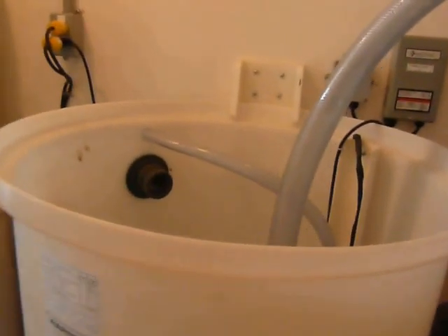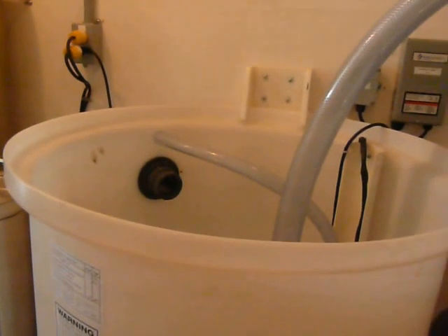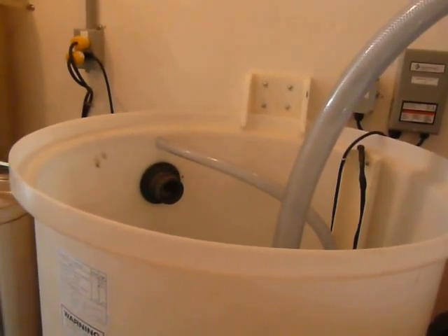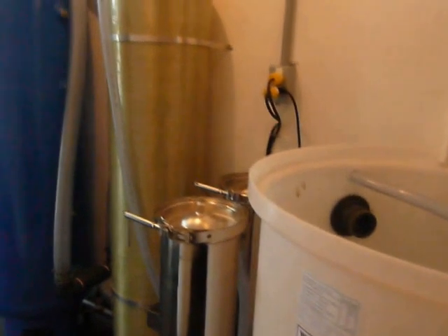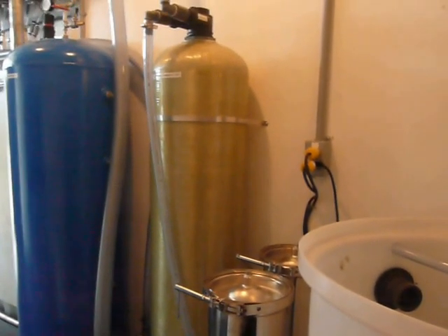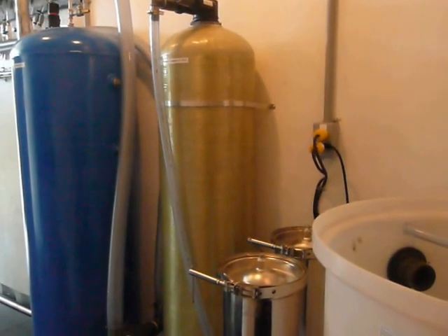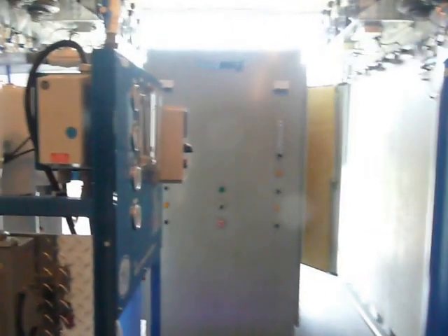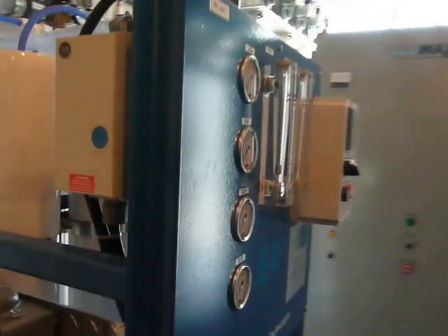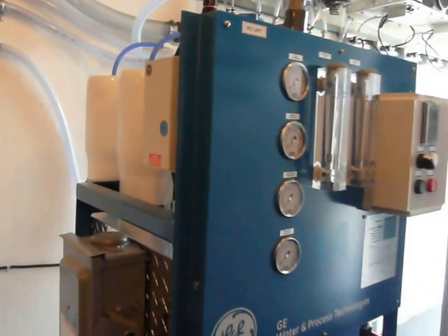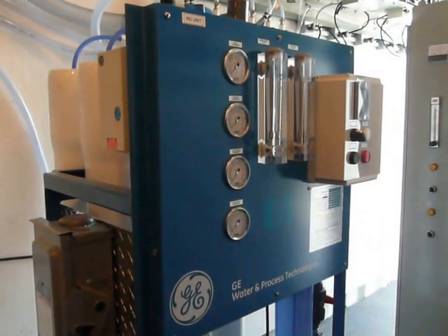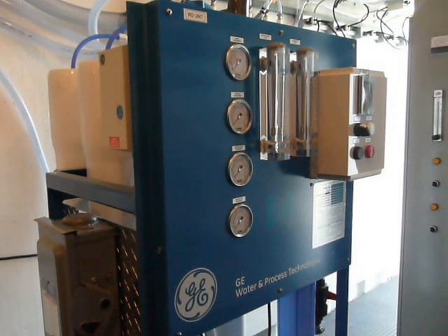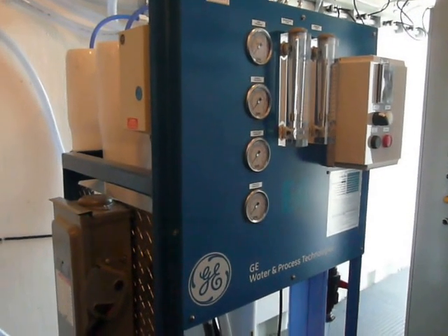Now this holding tank contains a submersible pump which directs the water into a series of filters to remove fine particles and also to remove residual ozone. And in this specific case, since we're treating FRAC water, there is some degree of salinity to the water, and so we are using here a reverse osmosis unit to remove the salt from the water.